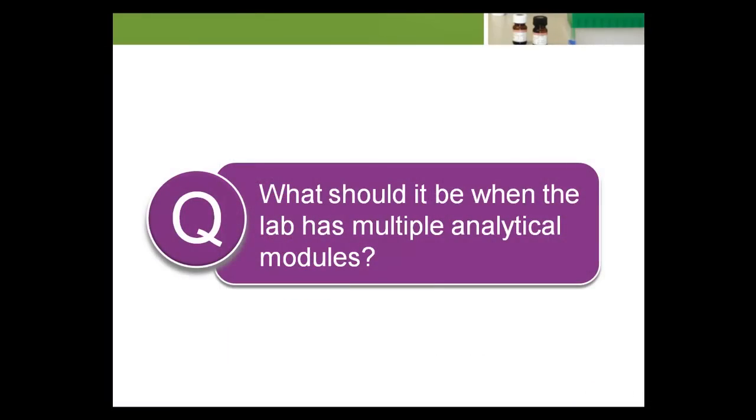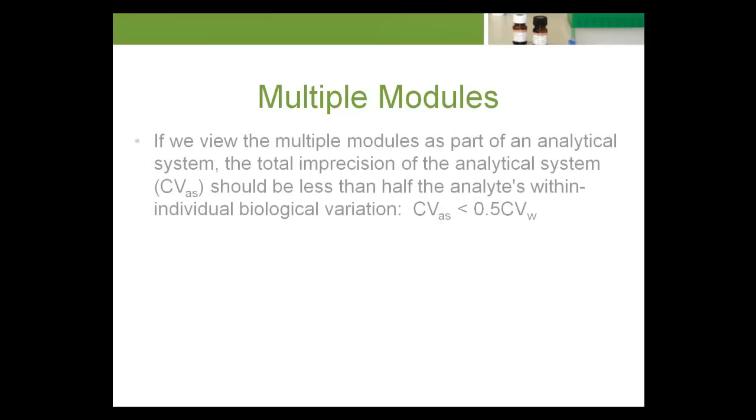If analytical imprecision should be less than half within-individual biological variation for a lab with a single instrument, what should it be when the lab has multiple analytical modules? Fortunately, the straightforward answer is the same. If we view the multiple modules as part of an analytical system, the total imprecision of the analytical system should be less than half the analyte's within-individual biological variation, CVAS less than 0.5 CVW.